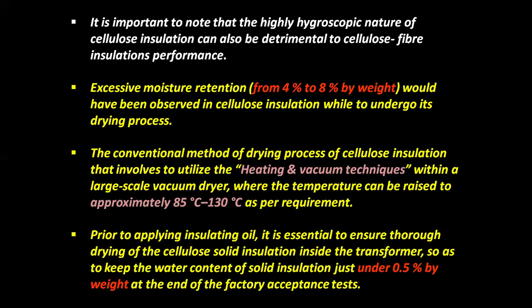The conventional drying process of cellulose insulation involves heating and vacuum techniques within a large scale vacuum dryer, where the temperature can be raised to approximately 85 degrees centigrade to 130 degrees centigrade as per requirement or as per class of insulation.